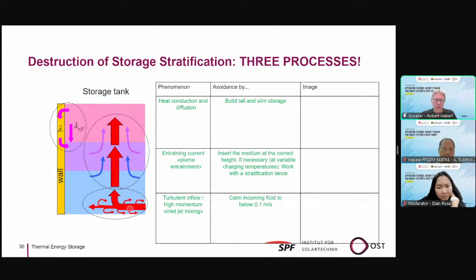And the third and most important is this that is shown here, the turbulent inflow with a high momentum, and it's called the inlet jet mixing. That is especially true with heat pumps, because heat pumps work with a low delta T and high flow rates, meaning you have only 5 Kelvin between return and supply, but you are very quickly at like 2 cubic meter per hour with a 10 kilowatt heat pump. And that inlet jet mixing destroys the stratification in the storage tank.